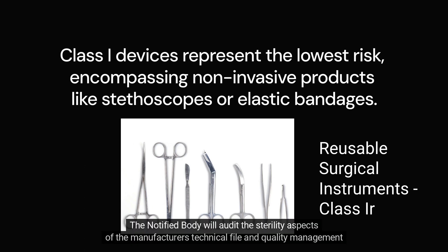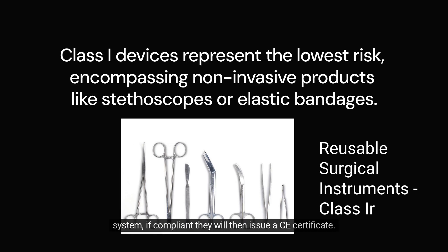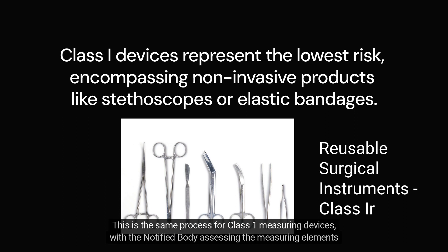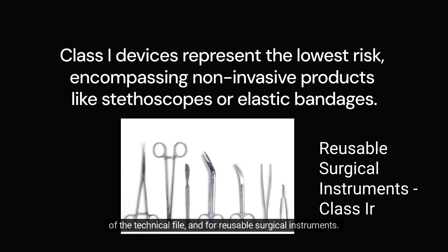Class 1 sterile devices must be assessed by a notified body. The notified body will audit the sterility aspects of the manufacturer's technical file and quality management system; if compliant, they will issue a CE certificate. The same process applies for class 1 measuring devices, with the notified body assessing the measuring elements of the technical file, and for reusable surgical instruments.